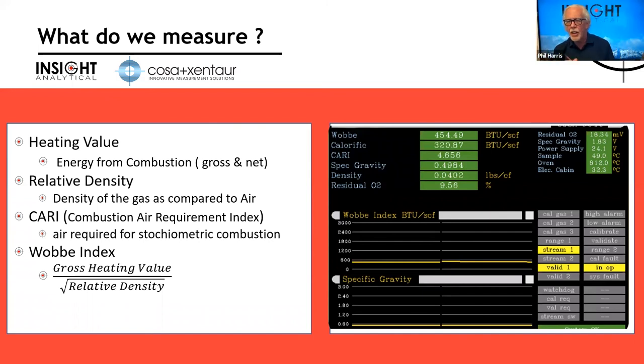And if we do that, what we can do on these types of analyzers is measure the heating value of the fluid. This also is going to require a density measurement. We can measure relative density, the density of the gas as compared to air. We can measure what's referred to as CARI, the combustion air requirement index, how much air is required to get exactly the right amount of air to burn this fuel. And then what we often end up controlling our burners off of is a thing called Wobbe Index. It's related to the gross heating value, but it's divided by the square root of the relative density.